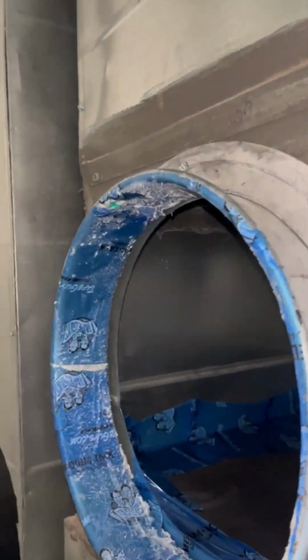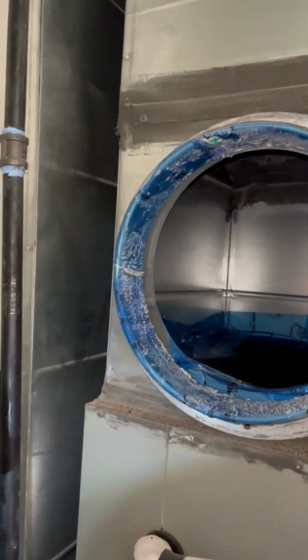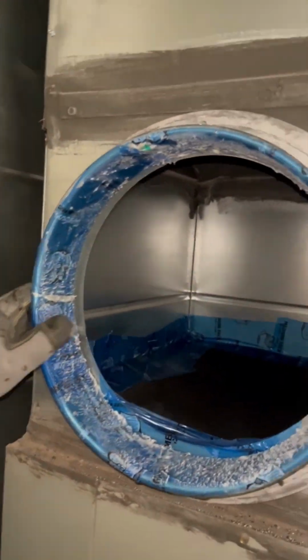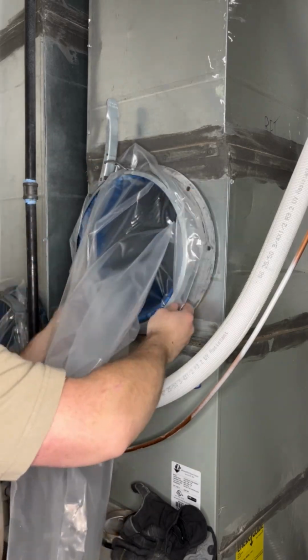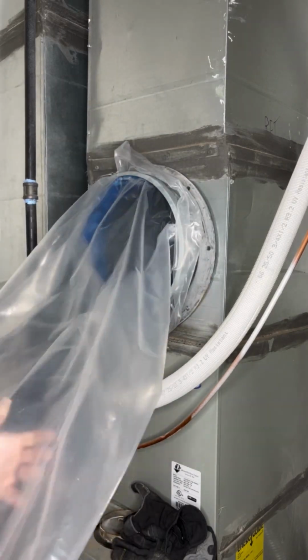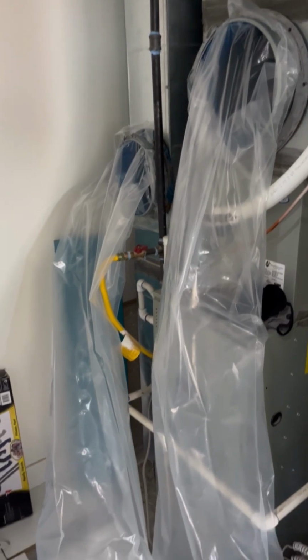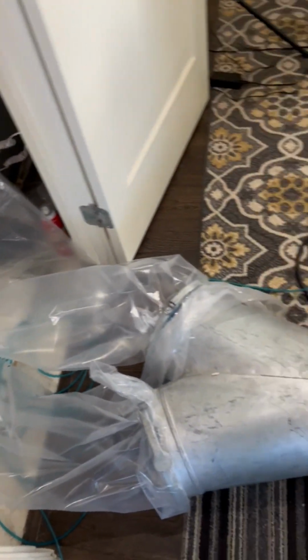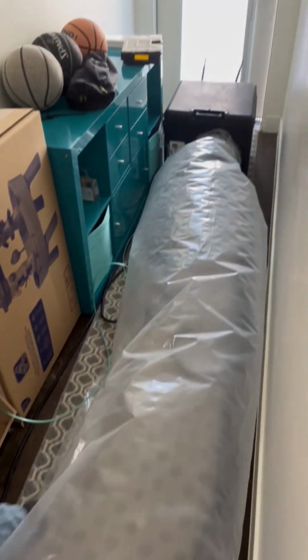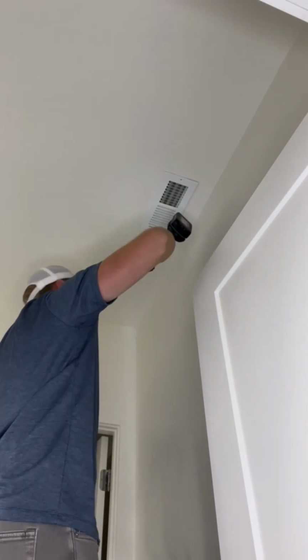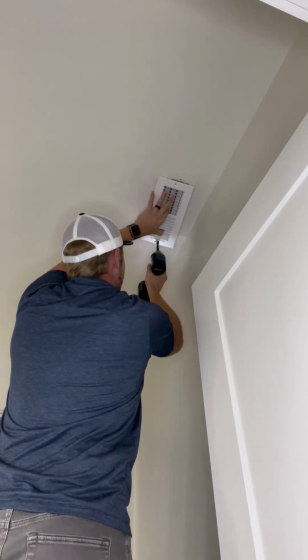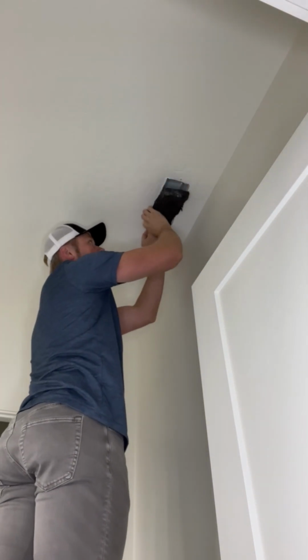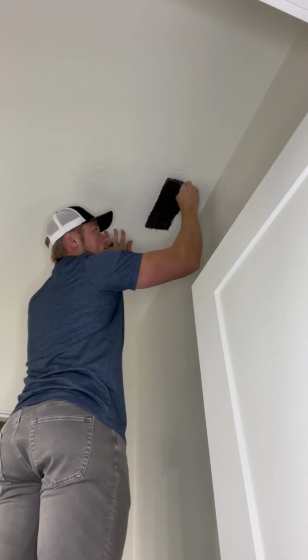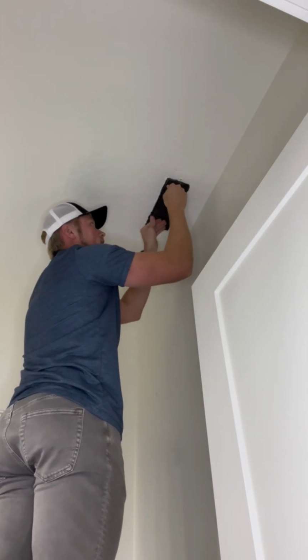This flange is used so that we can hook up a clear section of tubing that's used to actually inject the sealant. You can see here we're attaching that. We hook to the supply and return side, which goes into a Y-junction and then right into the fan box. It's equally important to have an airtight seal at the end of each supply and return vent. We use that same foam to put plugs into each vent opening.